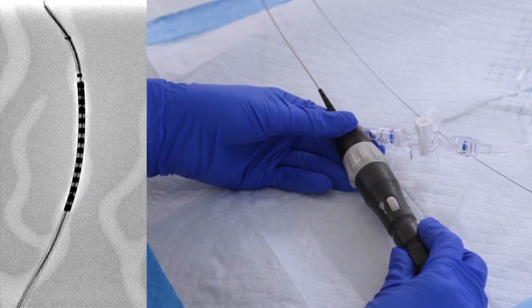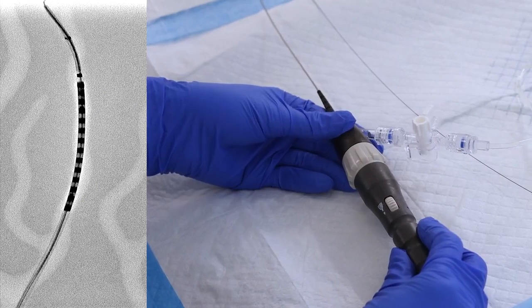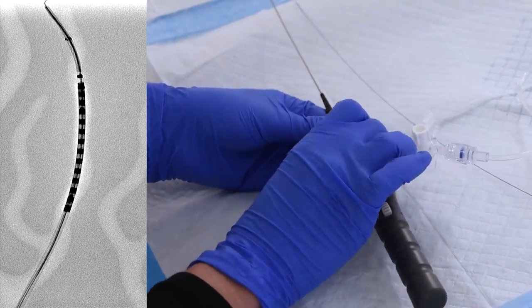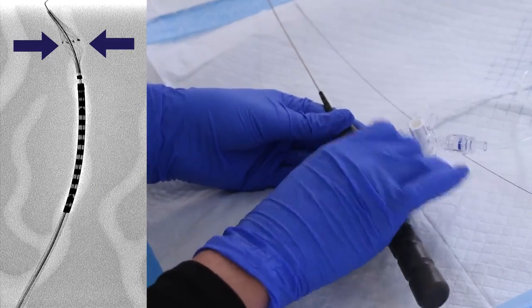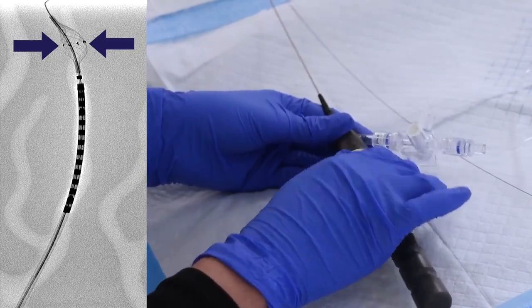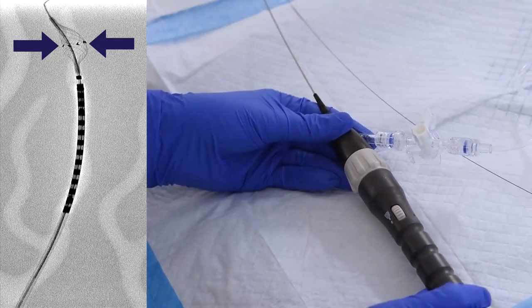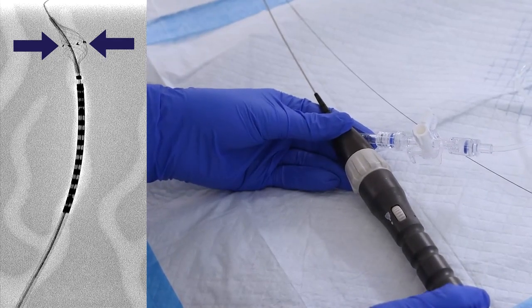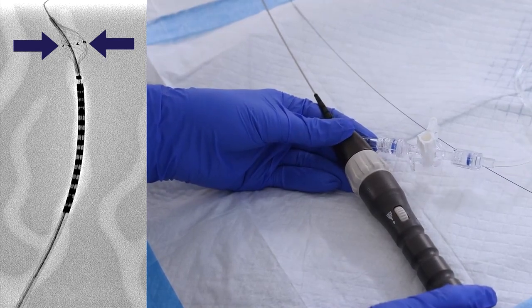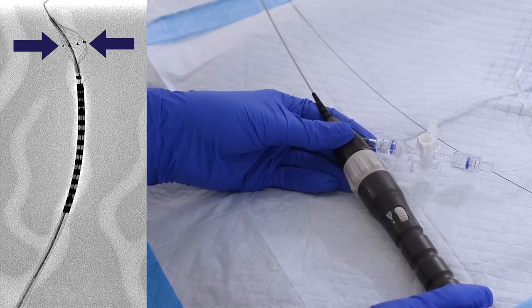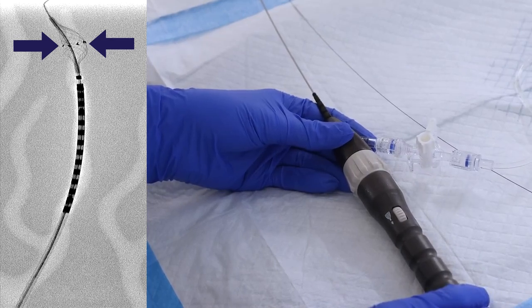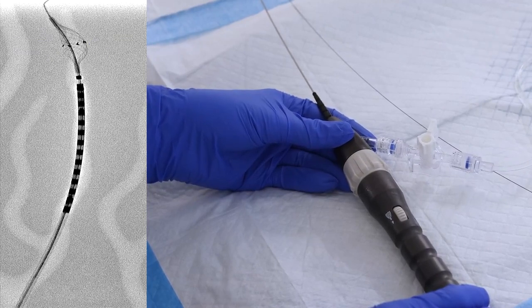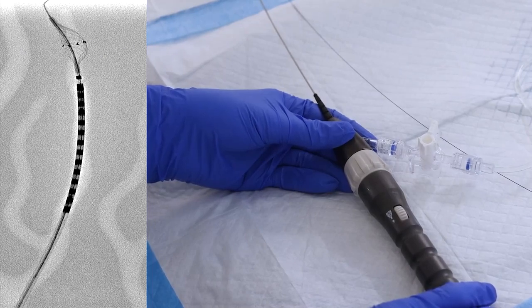Deploy the filter by slowly turning the filter deployment knob counterclockwise or to the left. There is no tactile feel to the filter deployment against the vessel wall. You will have to watch the 6 marker bands separate under fluoro. Verify that the filter is fully expanded and apposed to the vessel wall by visually confirming under fluoroscopy. Please caution, do not force the knob if it is not turning freely. Take care not to oversize the filter to minimize vessel trauma.